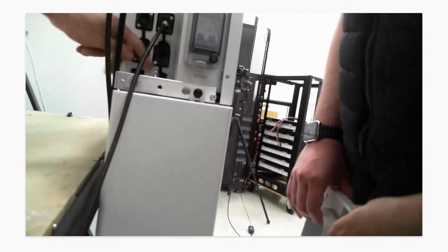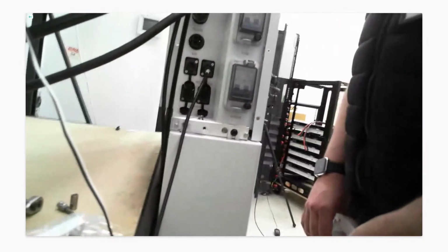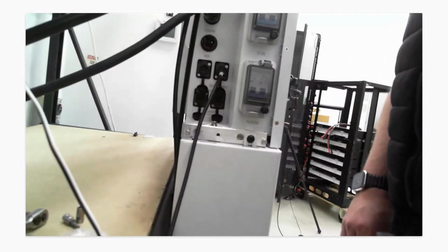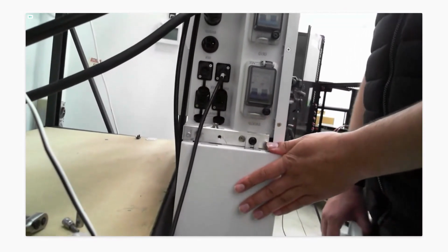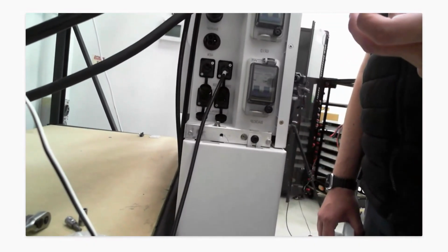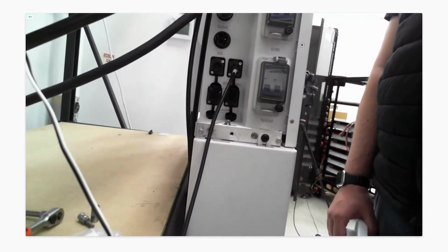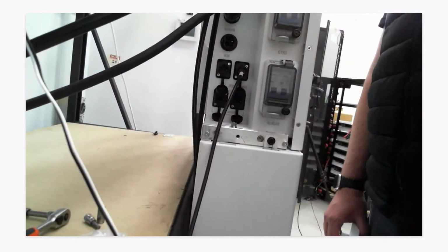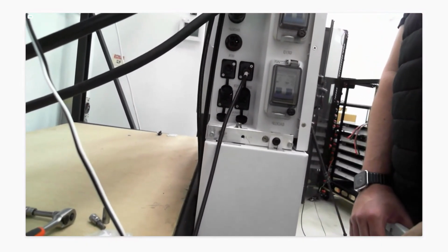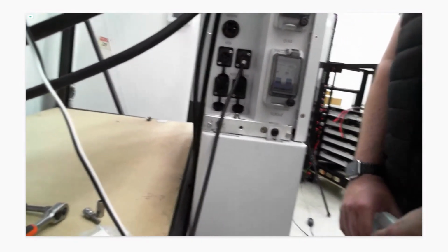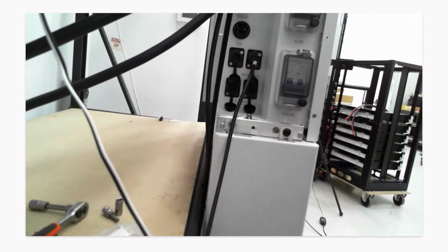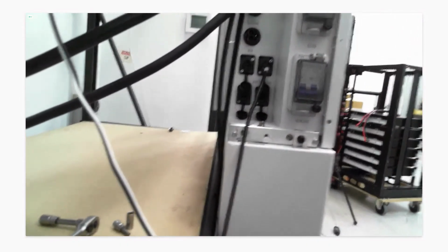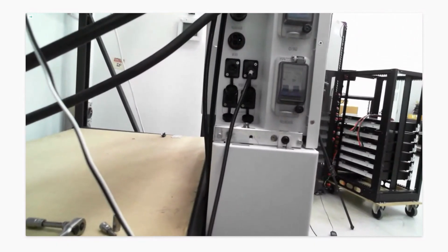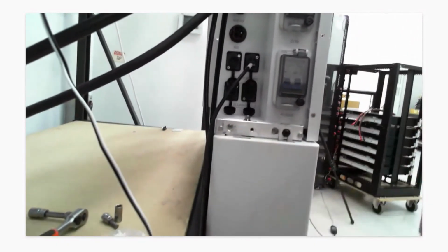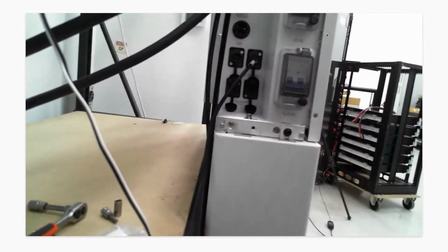And then down the bottom here, parallel. What's this for? These are currently not active for single phase. But for 3-phase, they're going to allow us to do real 3-phase backup. You could install one of these per phase. When you go into blackout mode, they only support physically the phase they're connected to, but the parallel connection will allow us to have synchronized 3-phase output. So if you have a 3-phase aircon or a 3-phase load, we will be able to run it. Is that available yet? It's available in the next 2 weeks, we believe. And you can unbalance the phases, because they've got separate single phase inverters and separate battery banks.